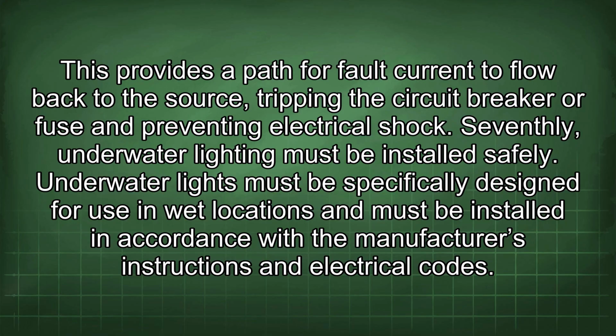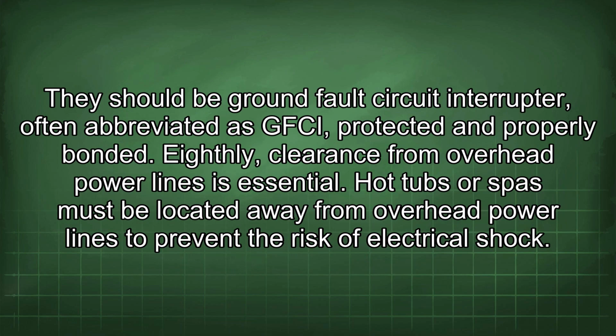Seventhly, underwater lighting must be installed safely. Underwater lights must be specifically designed for use in wet locations and must be installed in accordance with the manufacturer's instructions and electrical codes. They should be GFCI protected and properly bonded. Eighthly, clearance from overhead power lines is essential. Hot tubs or spas must be located away from overhead power lines to prevent the risk of electrical shock.